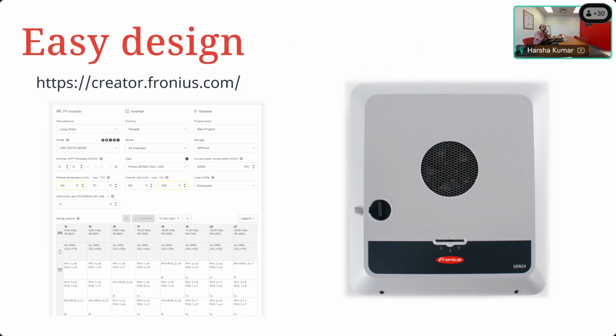But what you always want to do is to plug whatever numbers you have in mind through this tool while making sure that the numbers you're putting in here are relevant to us in Canada, and then making the right choice. And then the table that you see there, where you can see the numbers in bold, starting with 14, 15, 16, 17, 18, etc. The table beneath there is the suggested configurations of string designs, which are safe for working with this model of inverter. Okay, so this is where the tool has built, what should I say, it's got the device limitations worked into it. So you don't have to go through the hassle of understanding those device limitations.